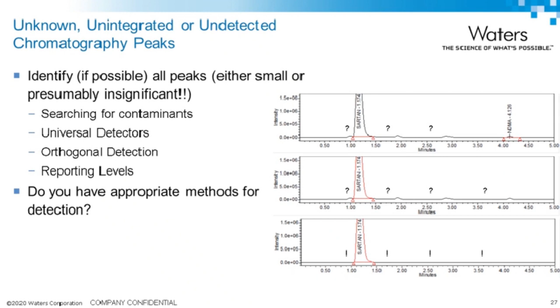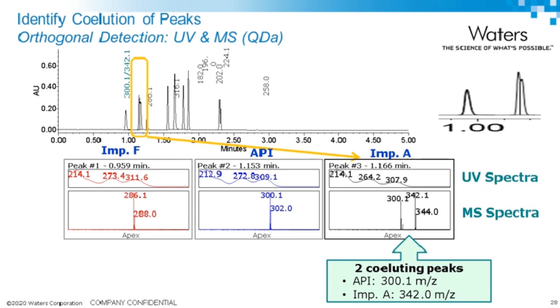Now, this is an example where using MS detection can show me that, where those two peaks are really not very well resolved, I can look at the mass spectra of those peaks and say they are definitely two different compounds. They're not just a split peak. I shouldn't be integrating them together, and I'm probably going to very much overestimate impurity A, because it's been contaminated in the chromatography with a lot of the API with a mass of 300. That extra information is enough to say, I put my hand up and I should say, there's something wrong with this analysis. I think I'm going to overestimate the impurity. I need to get a better method so I can separate these two peaks.